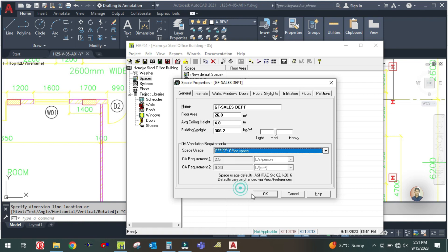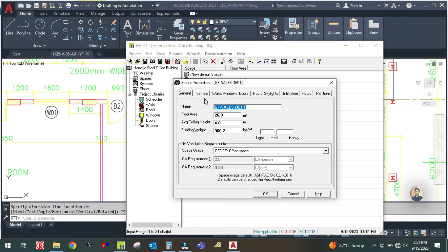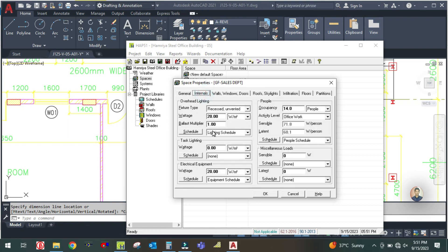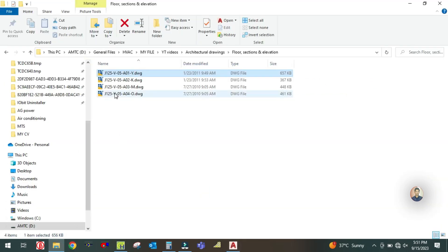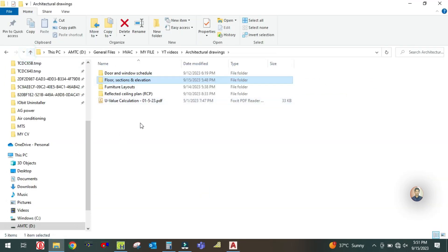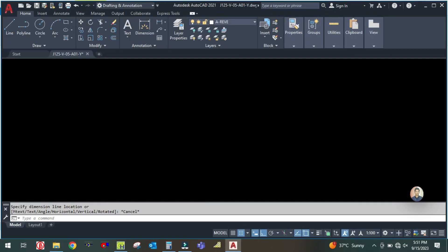Select office space, then click and go to the internal tab. In the internal type, the lighting load will be the same at 20 watts per square meter. Select the lighting schedule. The equipment load will be the same, there is no task lighting, and the number of people we can select from the furniture layout.